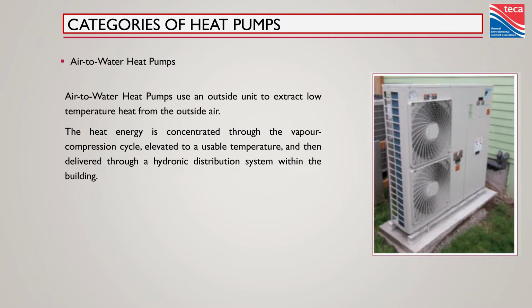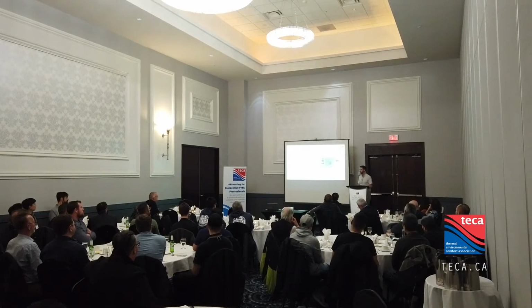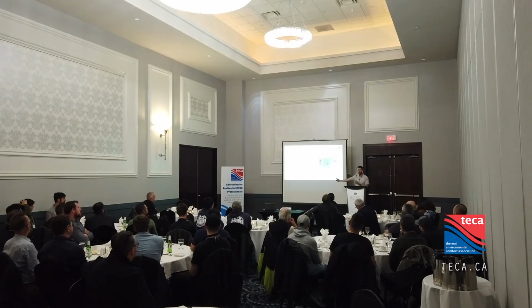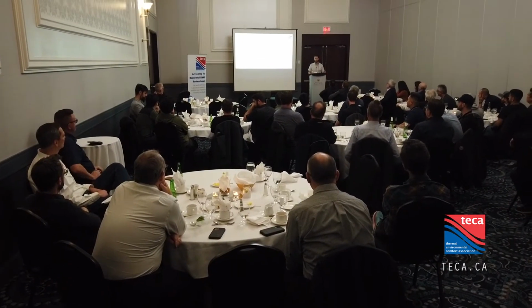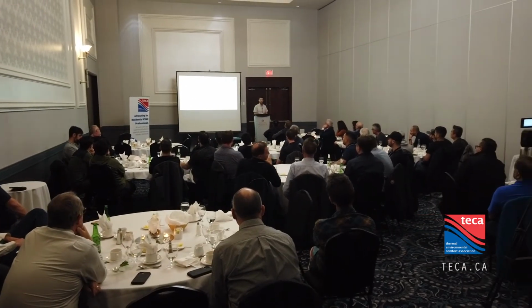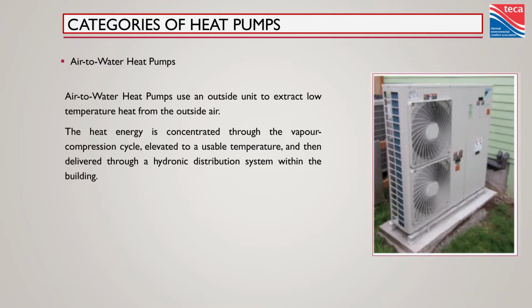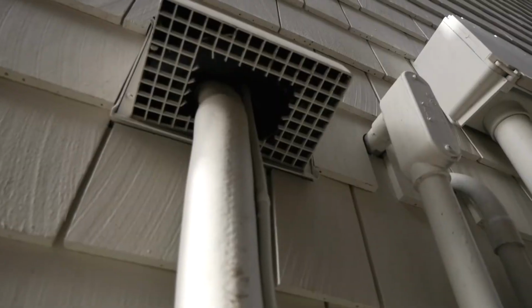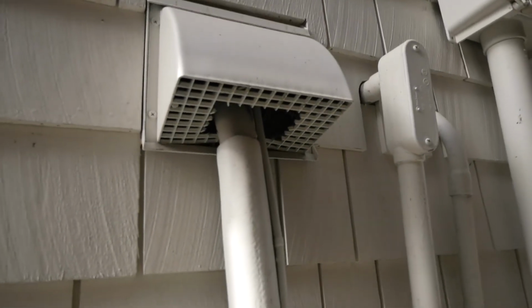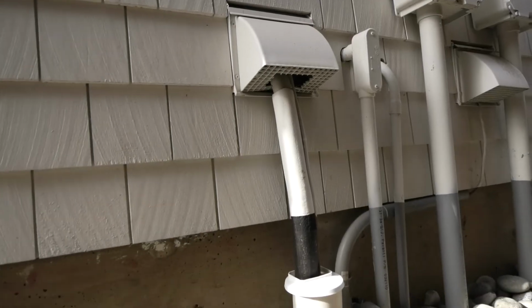Heating, cooling comes out. Thing with monoblock heat pumps is if you're a gas fitter plumber, this is probably right up your alley because you're already doing the plumbing side of things. You don't need a refrigeration contractor involved to run line sets, charge it, whatnot. It comes factory charged, ready to go. But we have water lines outside now, and believe it or not, it gets cold everywhere at some point in the year, and that water can freeze. So the key part with any monoblock heat pump is glycol. We're going to have to use glycol in these things to protect them from freezing. Glycol does one thing really well, it doesn't freeze. So you can count on that.